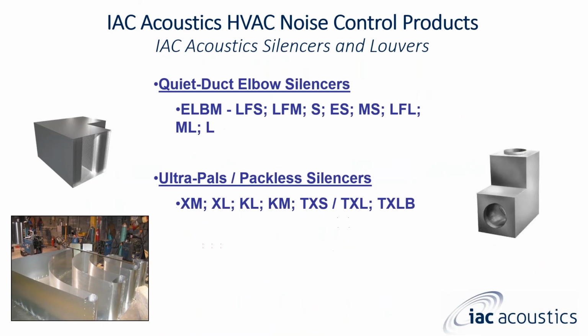We have what is becoming ever so popular now, our quiet duct elbow silencers. Down on the bottom left, you can see how we actually build our elbow silencers. The turning vanes are actually part of the inner baffles. This helps with airflow movement, and at the same time it helps keep pressure drop low.